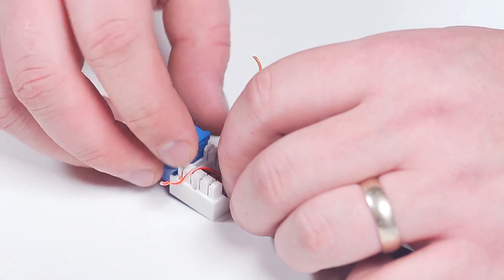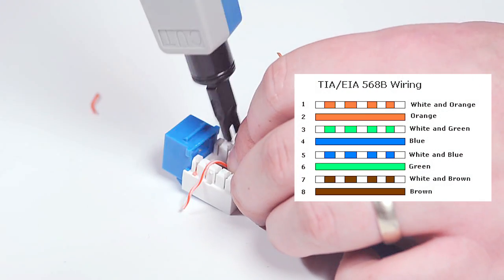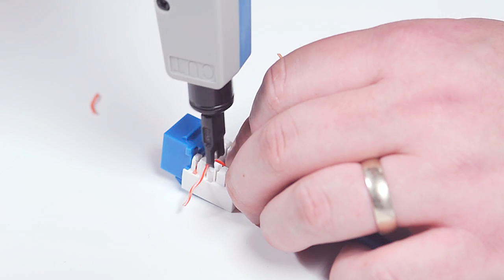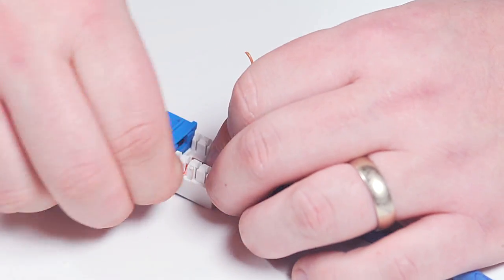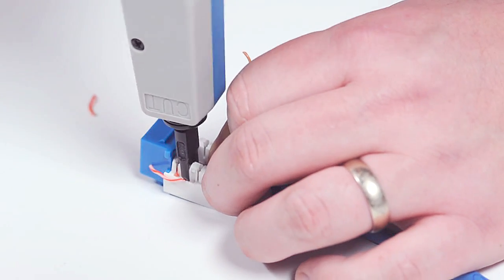For most applications, choose the 568B color code. Once you have laid out the conductors to the right color code, take your impact tool and punch down the conductors. The punch down tool pushes down the conductors into the IDC slot and also removes extra wire.